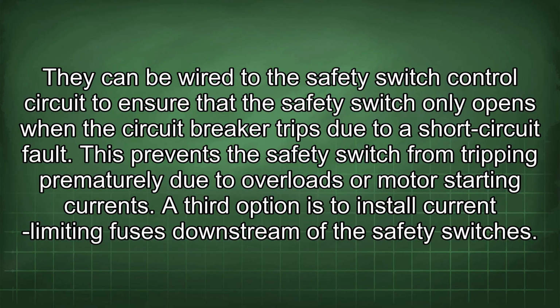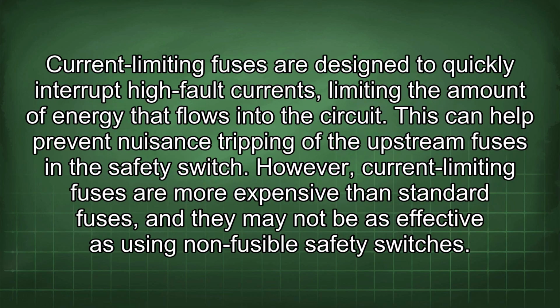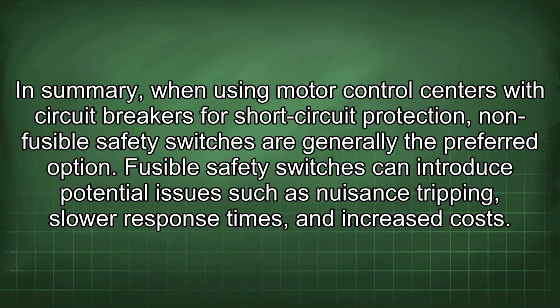A third option is to install current limiting fuses downstream of the safety switches. Current limiting fuses are designed to quickly interrupt high fault currents, limiting the amount of energy that flows into the circuit. This can help prevent nuisance tripping of the upstream fuses in the safety switch. However, current limiting fuses are more expensive than standard fuses, and they may not be as effective as using non-fusible safety switches.